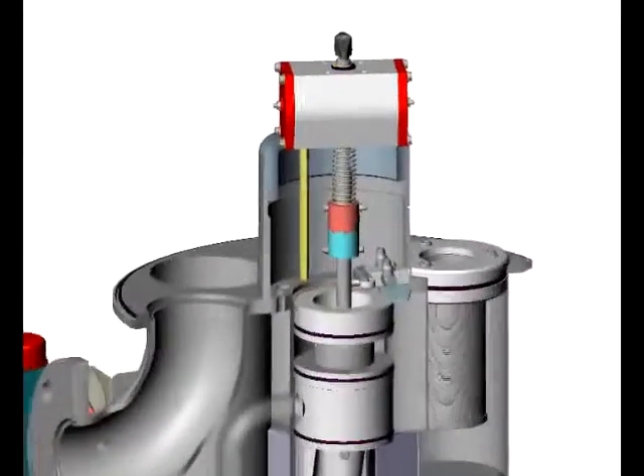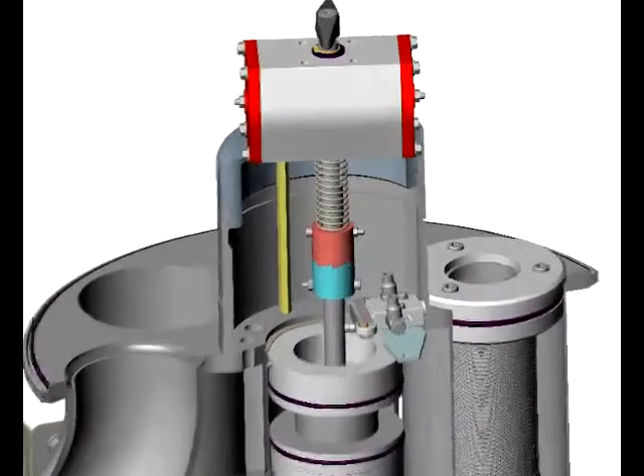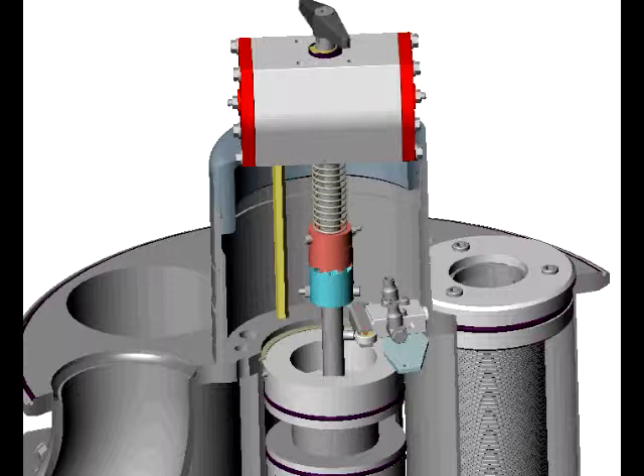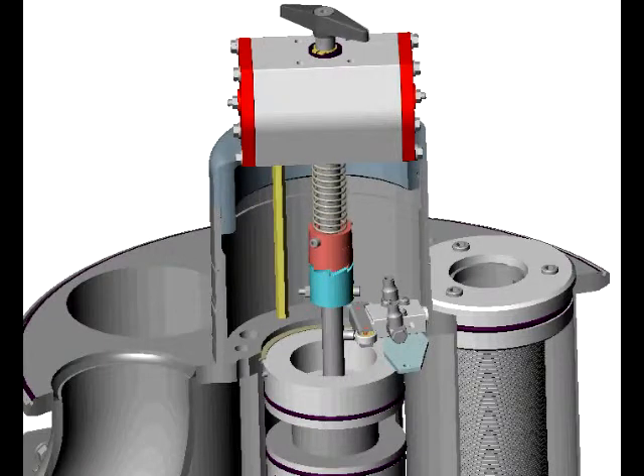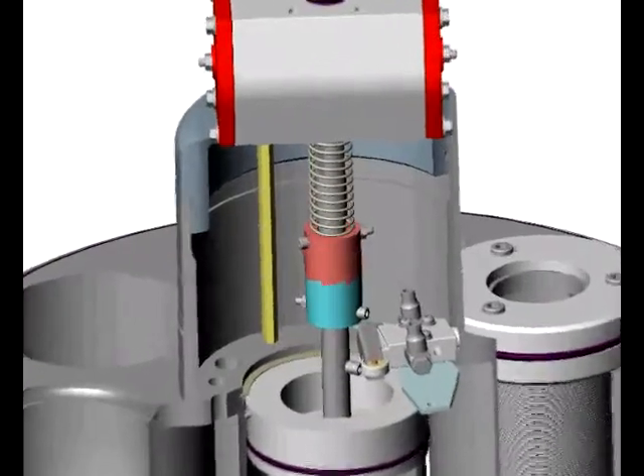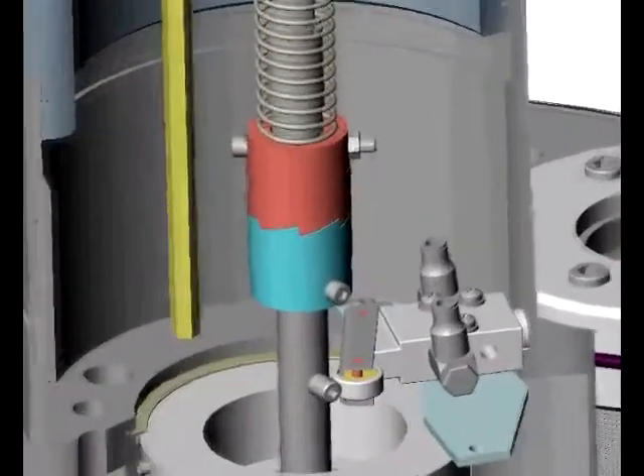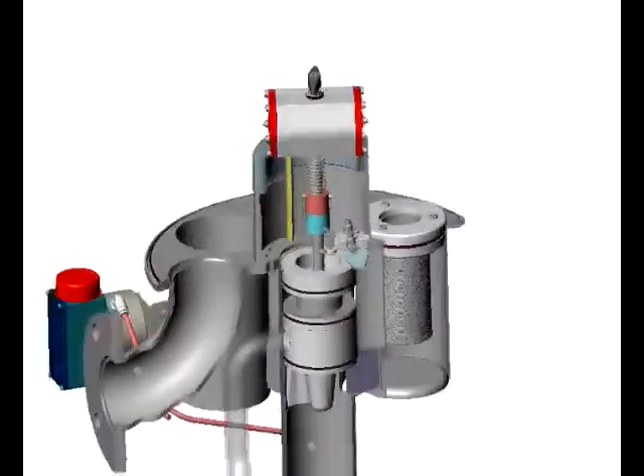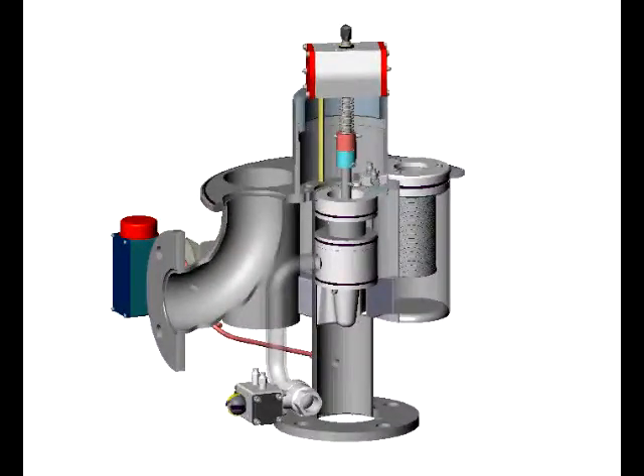The backwash process by following the motion at half speed. First, the indexing actuator rotates 90 degrees counterclockwise and the dog teeth ratchet up and over each other. After a short pause, the indexing actuator rotates 90 degrees clockwise and the dog teeth engage. In this way, the lower drive shaft is rotated through one seventh of a revolution. Notice also how the home switch roller arm has dropped down off the protruding screw, telling the control system that the indexing valve is no longer in the home position.